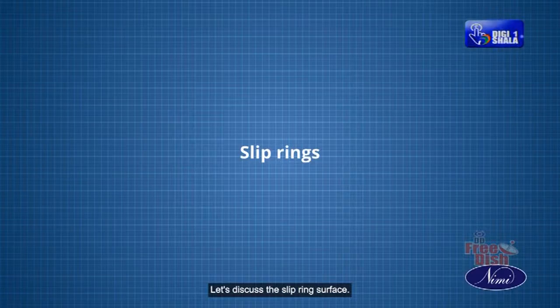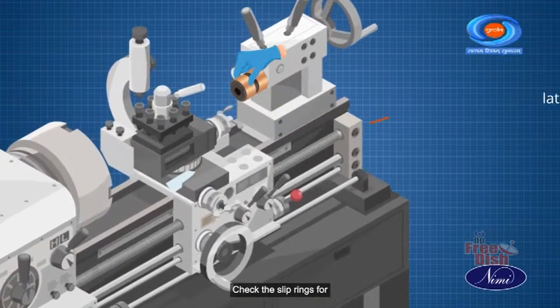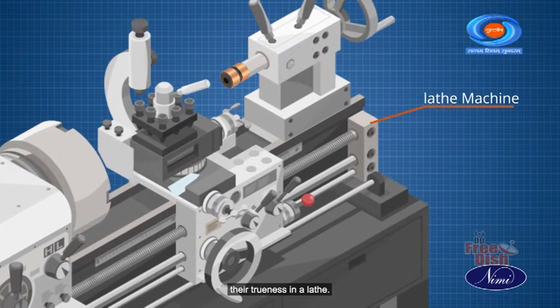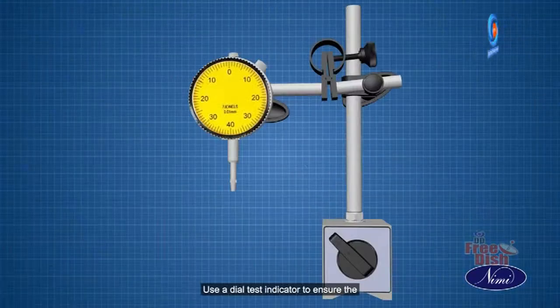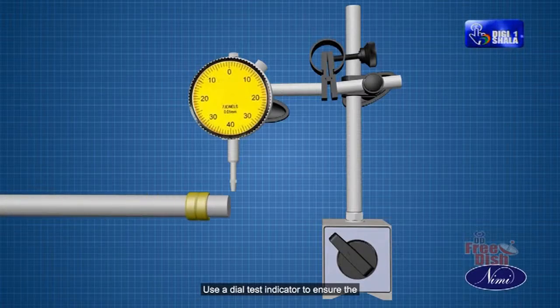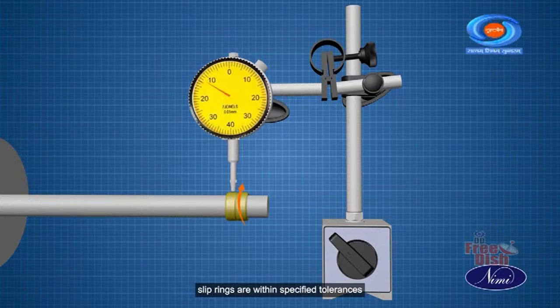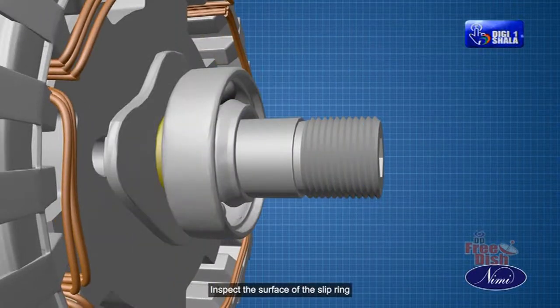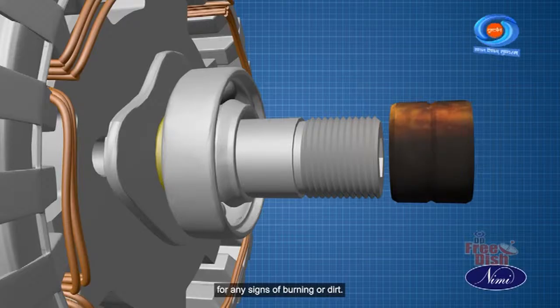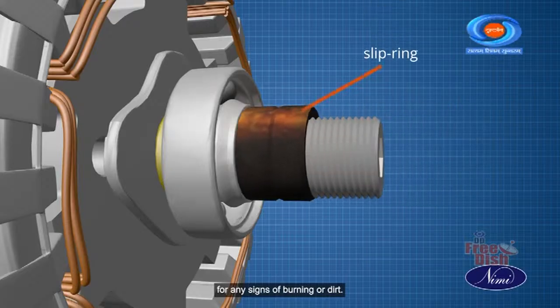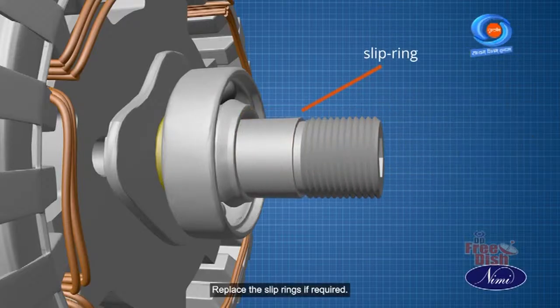Let's discuss the slip ring surface. Check the slip rings for their trueness in a lathe. Use a dial test indicator to ensure the slip rings are within specified tolerances for roundness and concentricity. Inspect the surface of the slip ring for any signs of burning or dirt. Replace the slip rings if required.